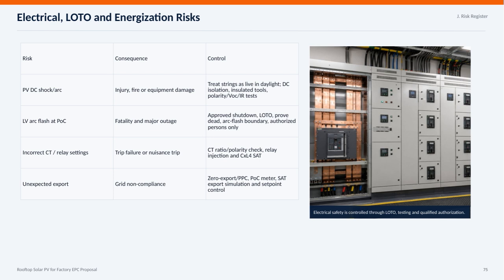Incorrect current transformer or relay settings can cause trip failures or nuisance trips. We mitigate this risk by verifying CT ratios and polarity, conducting relay injection tests, and performing commissioning level 4 site acceptance testing. Lastly, unexpected export to the grid can lead to non-compliance issues.